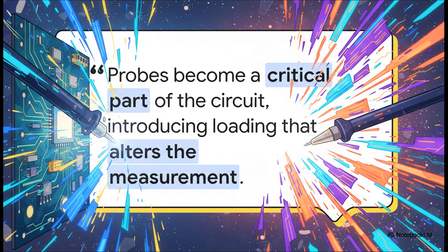We all tend to think of the probe as just a piece of wire, right? A passive observer, just listening in. But that is completely wrong. The second you touch that probe to your circuit, it literally becomes part of your circuit. It's not just watching the show, it's on stage, changing the performance.